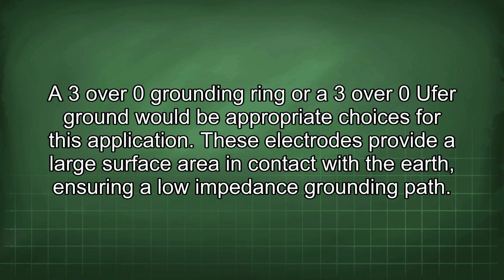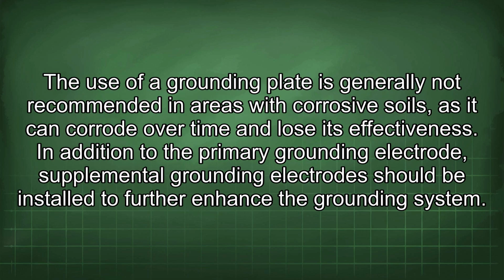These electrodes provide a large surface area in contact with the earth, ensuring a low impedance grounding path. The use of a grounding plate is generally not recommended in areas with corrosive soils, as it can corrode over time and lose its effectiveness.